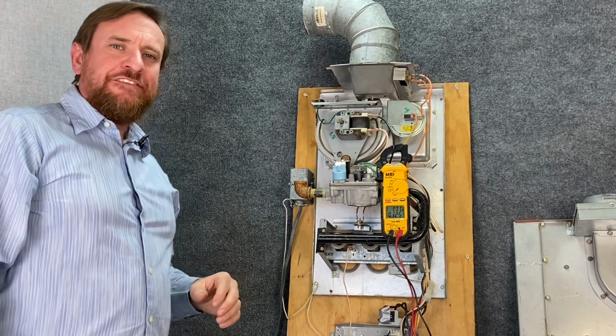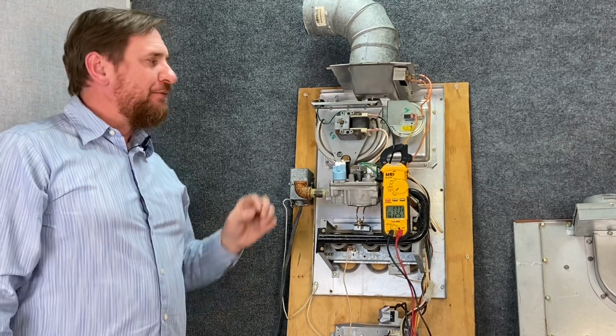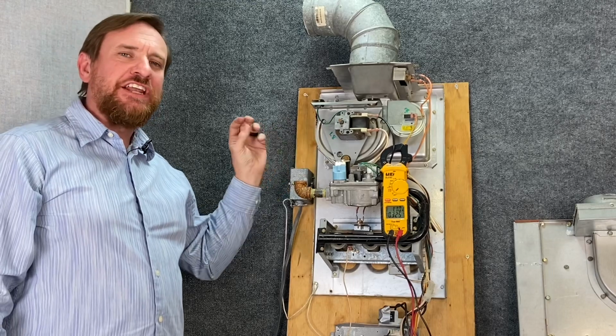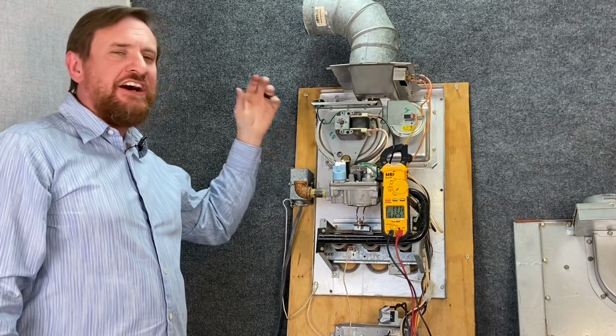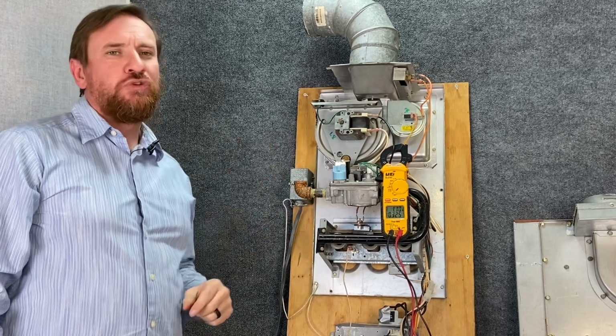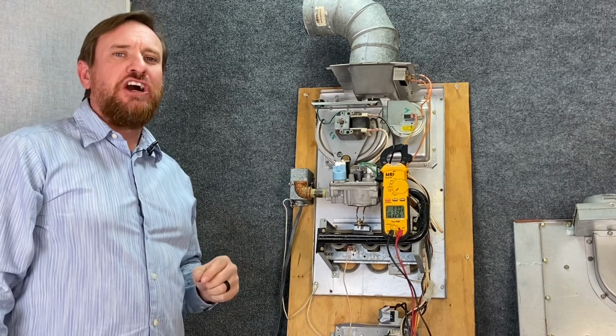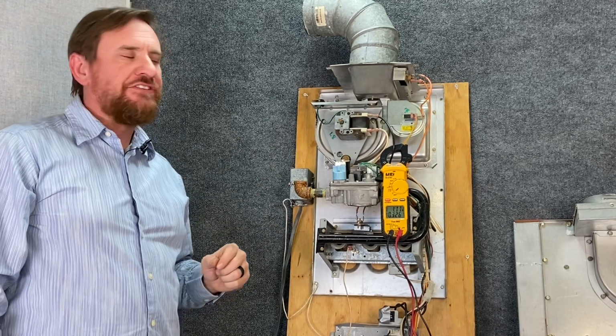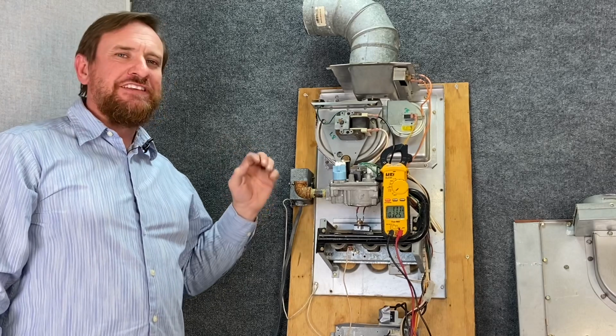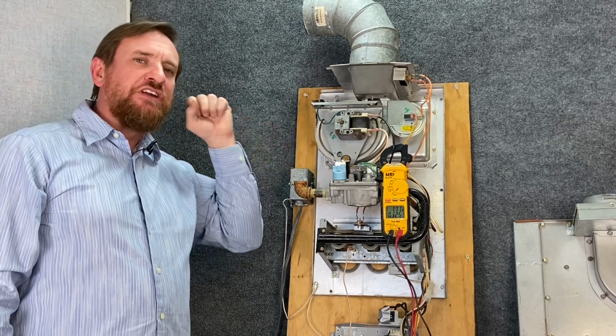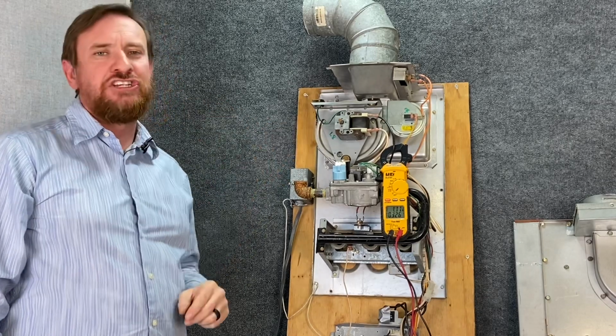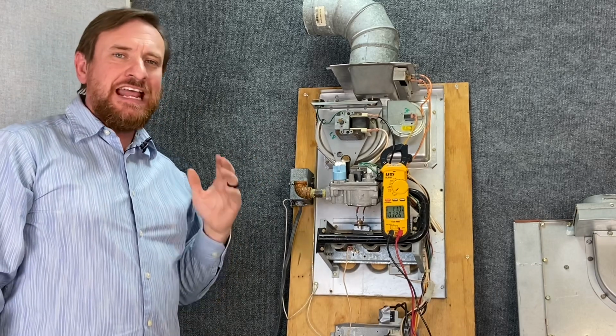Another thing that's likely to fail on these little inducer fan motor assemblies is the bearings. There's a lot of heat going on through here. It's pulling all that hot gas out, and these bearings are notorious for failing. Most of them are non-serviceable, non-oil bearings. So an old timer told me you could take your screwdriver, put it up against the motor and against your ear, and you can hear the condition of the bearings. And it's true. That absolutely works.